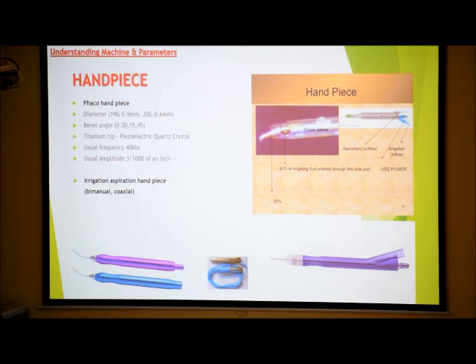Phaco handpiece is available in two different sizes. One is 19 gauge, which is almost 0.9 mm internal diameter, and 20 gauge, which is still thinner, around 0.6 mm internal diameter. It's also available in four different angles, that is beveling at the end of the tip. That is 0 degree, 15, 30, 45, and 60. And I will discuss later on how that helps in different grades of cataract. The titanium tip transduces electrical energy into mechanical energy that transmits into the hard nucleus and creates cavity, or transmits acoustic waves to help in breakdown of the hard nucleus.